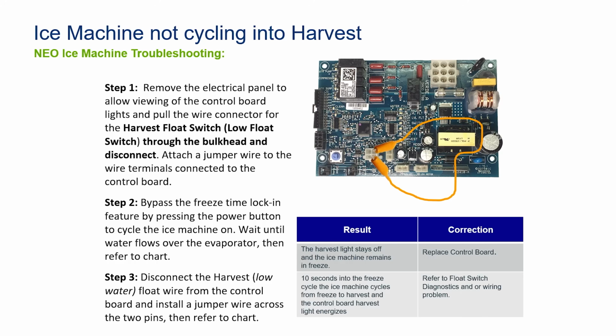I would probably recommend viewing another video, one of our Ice Tech FAQs, where we remove the bin. You can run the machine without the bin on, utilizing the test button. Go ahead and do all these things and force this machine to do what you need it to do, where you have room, or work around with whatever you need to do. If you do this and the machine goes into harvest, where you jump directly at the Molex, the unit goes into harvest, well, your problem is in one of the two, the harness or the float.